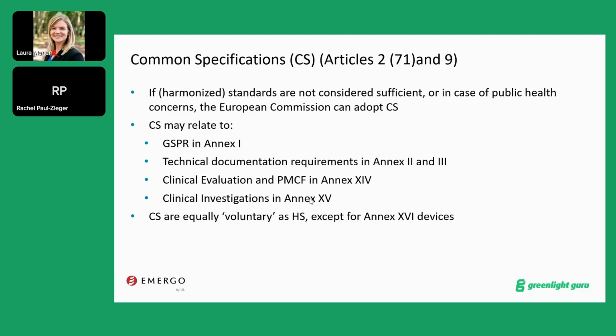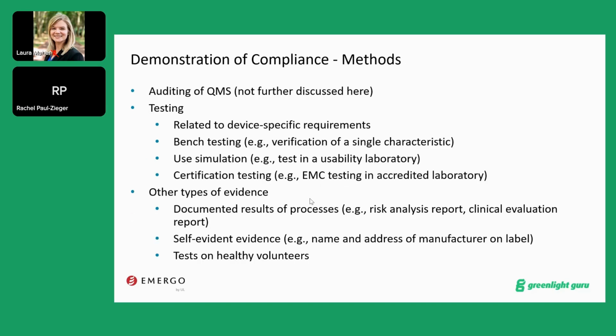This common specification may relate to GSPR in Annex 1, but also to technical documentation requirements in Annex 2 and 3, clinical evaluation and PMCF in Annex 14, clinical investigation in Annex 15. Common specifications are equally voluntary as harmonized standards. So these may be very powerful documents in the future.